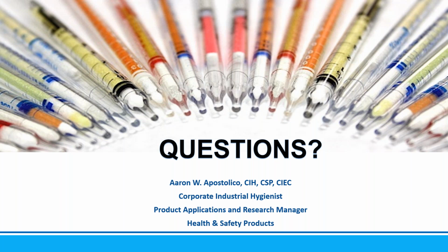So you reading it and me reading it could differ by several parts per million or milligrams per liter, depending on what the scale is, just based on how it was feathered at the time that the sample was taken. So that's really why they give that wide range of plus or minus 25%. If it is a good sample, it's easy to read. Most certainly the accuracy can be much, much better than plus or minus 25%.